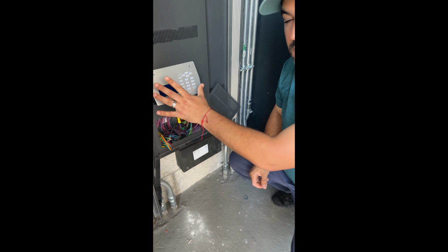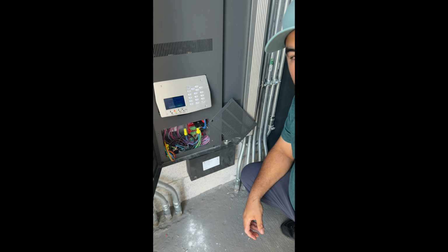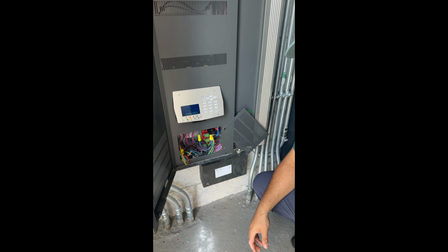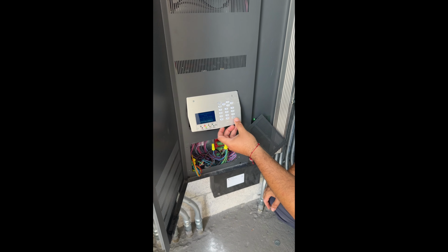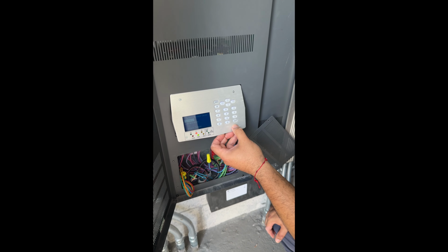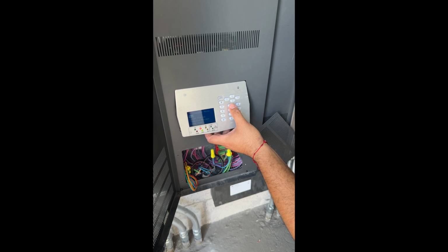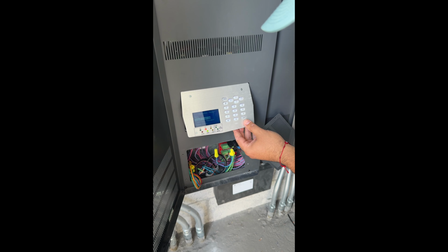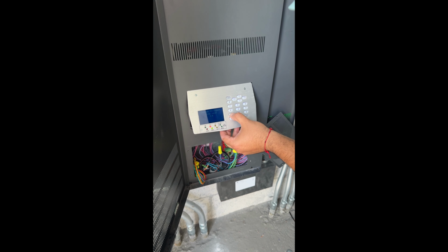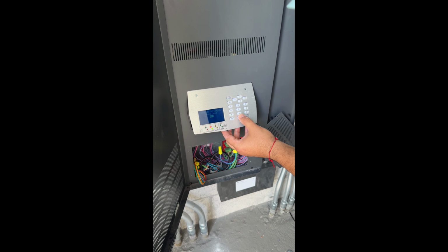Through this keypad, we can access the lighting control panel where they can override all the relays or each individual relay. In addition to it, they can edit and create new time events. The first thing we're going to do is override all the outputs, all the relays. We're going to hit enter, go to operation, go to output override, all outputs, and type 100 to go to 100%.